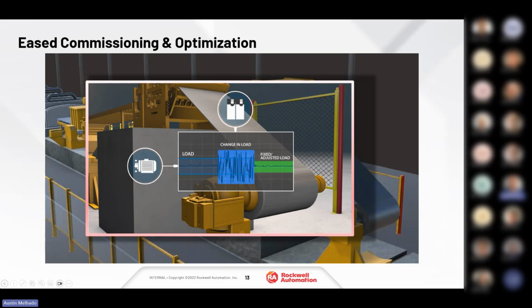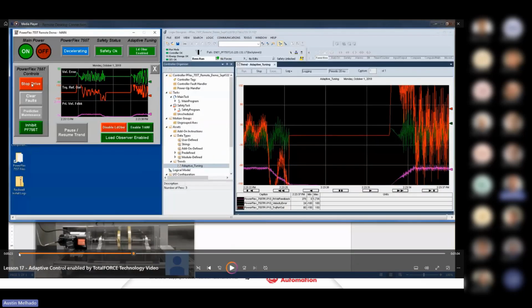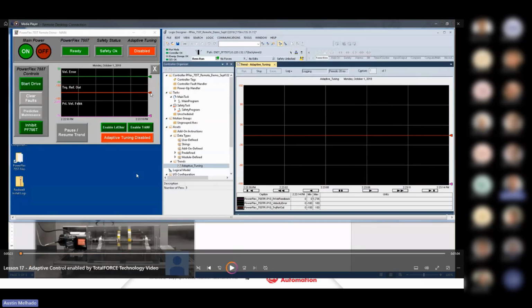With these features, I'll show exactly what that means. In this video, we have three different trends. For lack of better words, the green represents our low frequency side, the changing load, and the red represents our motor bearings, the high frequency side. With adaptive tuning and load observer, which monitors the load and also changes the notch filters, we're able to mask those resonance frequencies.